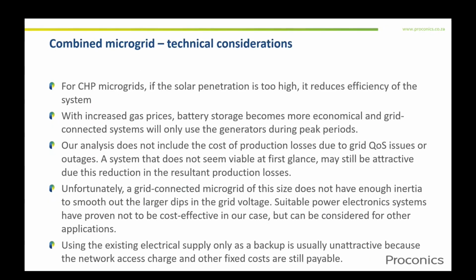Okay, now just some technical considerations, some points we picked up and learnings from this. For CHP microgrids, if the solar penetration is too high, it reduces the efficiency of the system. Now, this might sound counterintuitive, but because you are using waste heat from your generators as part of your process heat, you will have less process heat available if you throttle back your generators, if you have too much PV. So because we are looking at the overall efficiency, we need to take that into account. And fortunately, the software helps a lot with that, because it can be quite a tedious calculation otherwise.